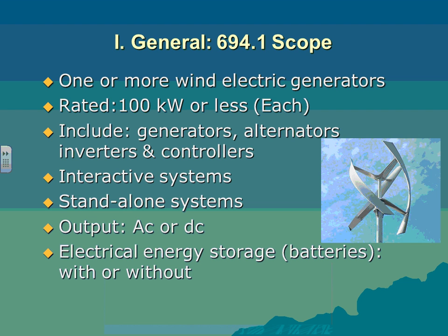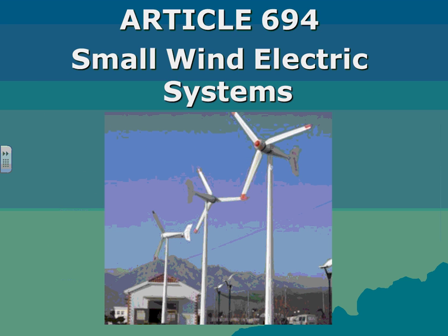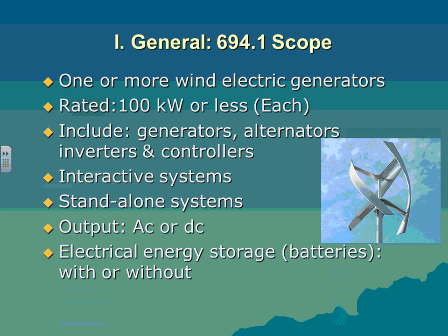A few things about this article, my friends, if you're not familiar with it: it handles one or more wind electric generators. They can look in any shape or form. Typically, this is the typical look for these systems, but they're limited. This article covers up to 100 kW. So if you're looking for 2 meg, 3 meg and 4 meg, this article is not for you. You have to have an engineered project. And that's where the engineers jump in and size all the system. And if anybody is interested, there's a lot of information about the 2 meg. But this particular article covers 100 kW or less.